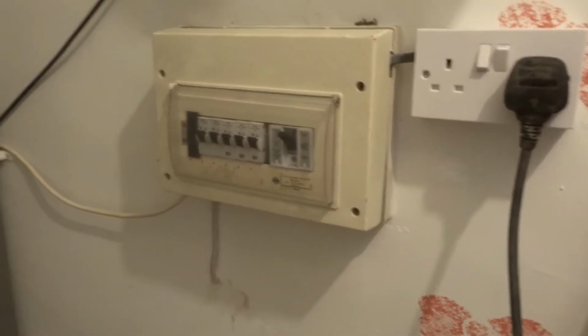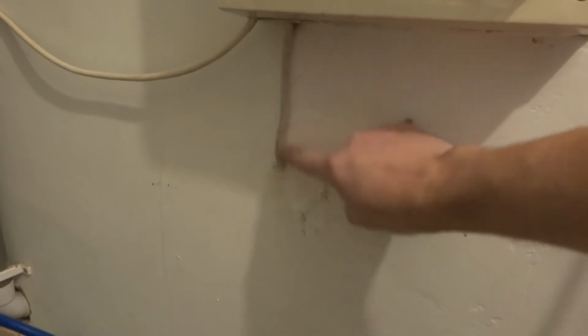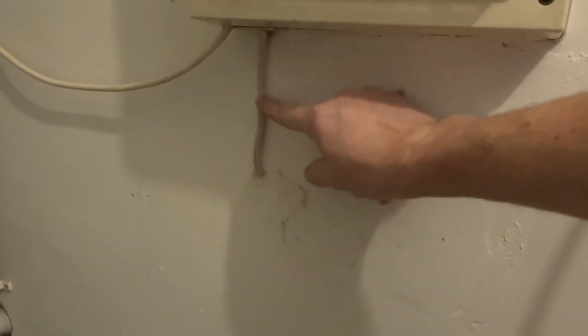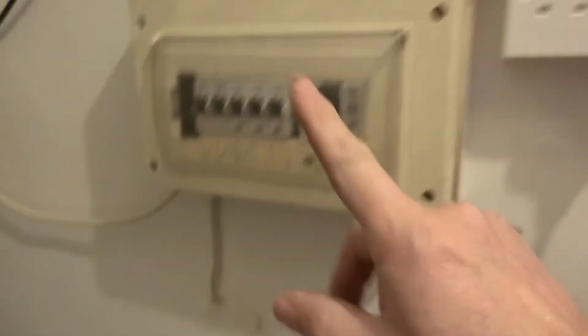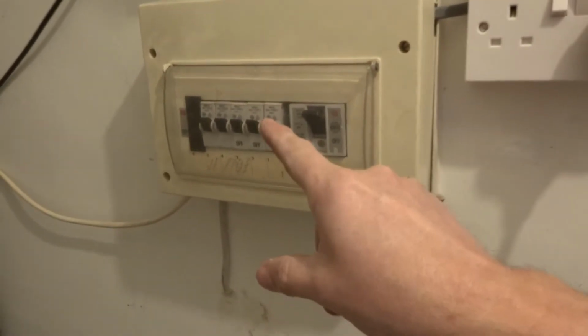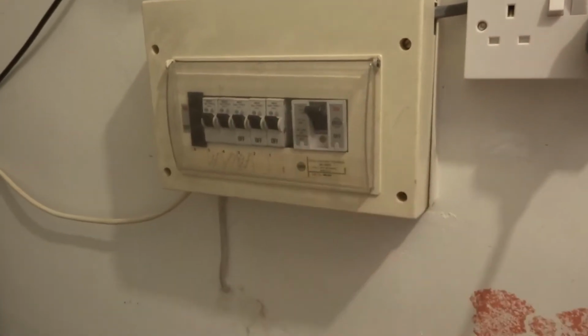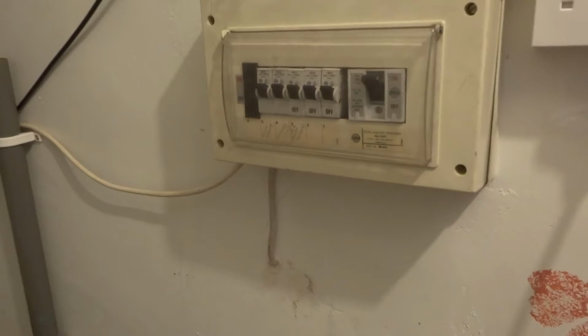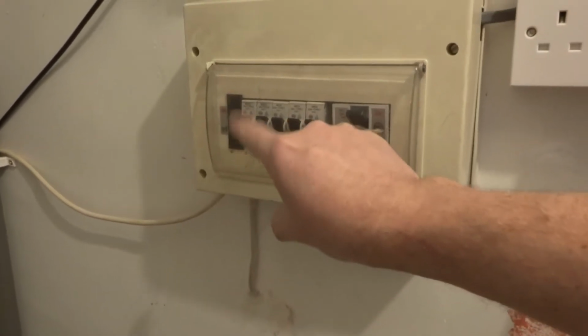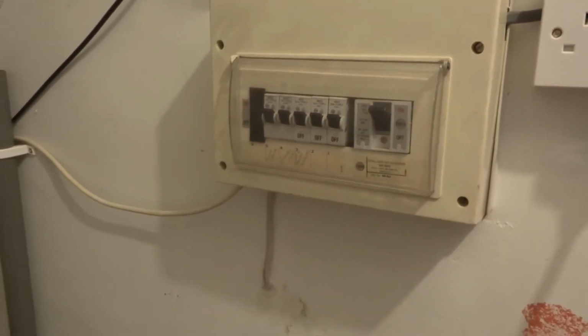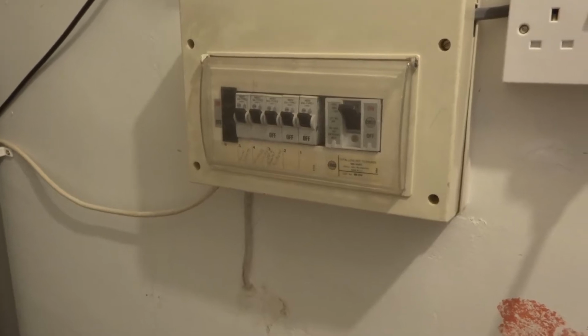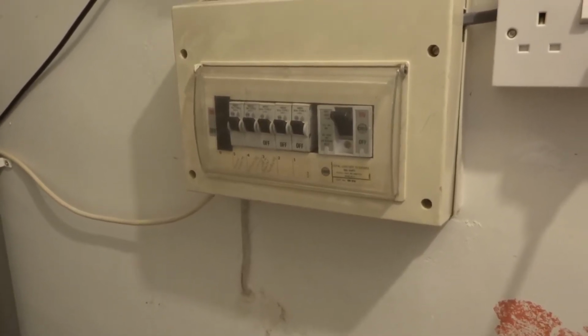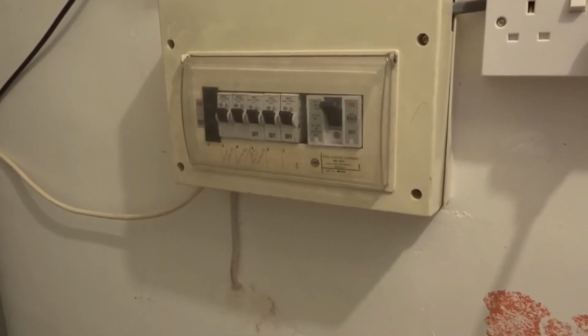So the plan is, this is the original wire - this is the original cable. It's like an aluminium sheath with just two wires in it, but all they've done is tapped it into standard mains breakers. I'd like to put another breaker into where that little black blanking piece is, to have an independent supply down to the garage, which I can turn off if we're going away, without isolating the whole house.